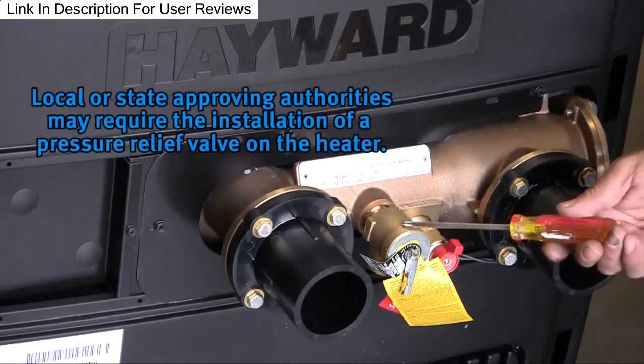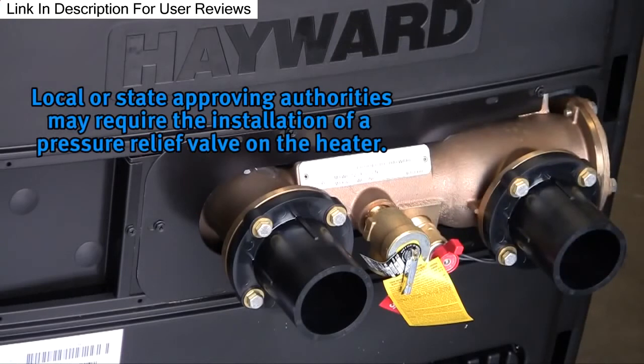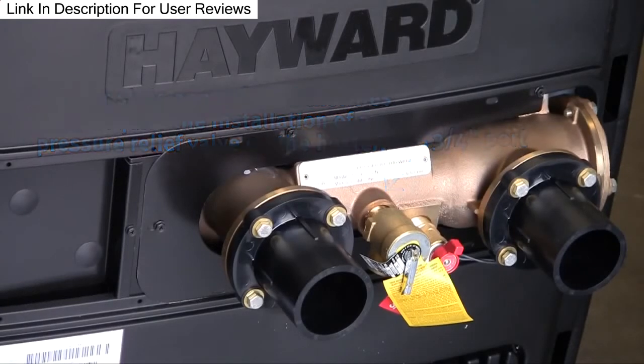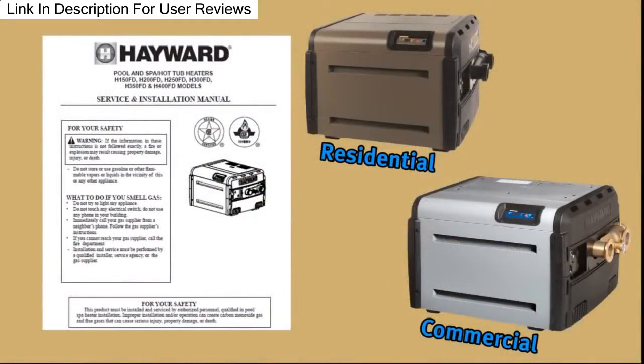Some local or state approving authorities may require a pressure relief valve to be installed on the heater. If one is required in your area, the header has a 3/4 inch port for this purpose. See installation manual for more information on installation and sizing of pressure relief valves. A relief valve must be ordered separately for the residential heater. The commercial heater comes equipped with a relief valve.